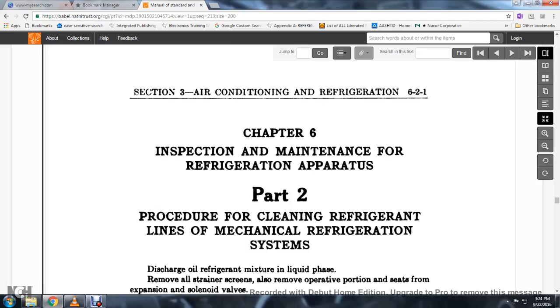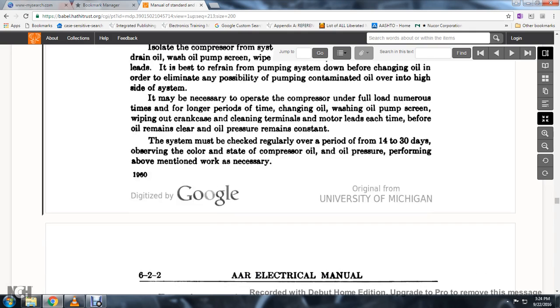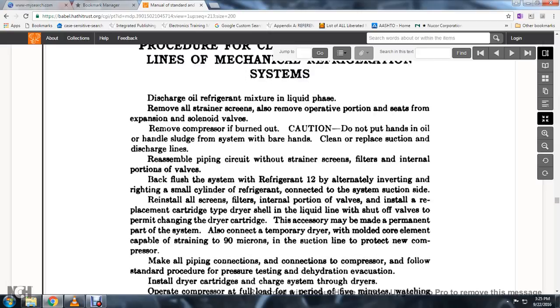Chapter 6, Inspection and Maintenance for Refrigeration Apparatus, Part 2: Procedure to clean the refrigeration lines in mechanical refrigeration. Discharge the oil-refrigerant mixture from the liquid phase. Remove all strainer screens. Remove all operative portions and seats from the expansion and solenoid valves. Remove the compressor if burned out. Caution: do not put hands in the oil or hand-contact sludge from the system with bare hands. Clean or replace the suction and discharge lines. Reassemble the piping circuit without strainer screens, filters, or internal portions of the valves. Back-flush the system with refrigerant 12, alternately inverting the small cylinder refrigerant container. Exit the system from the suction side. Reinstall the oil strainer filters and internal portions of the valves.